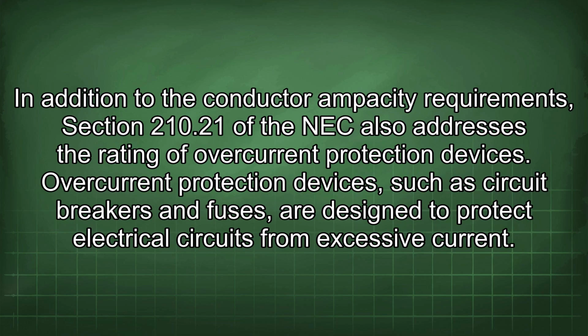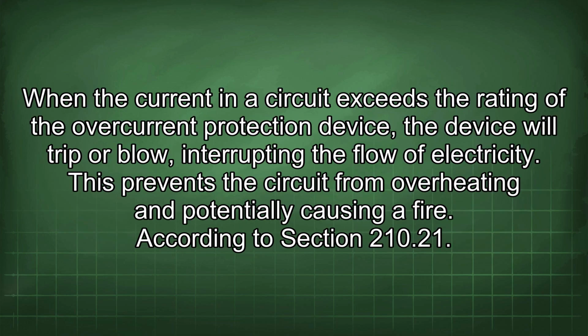In addition to the conductor ampacity requirements, Section 210.21 of the NEC also addresses the rating of overcurrent protection devices. Overcurrent protection devices, such as circuit breakers and fuses, are designed to protect electrical circuits from excessive current. When the current in a circuit exceeds the rating of the overcurrent protection device, the device will trip or blow, interrupting the flow of electricity. This prevents the circuit from overheating and potentially causing a fire.